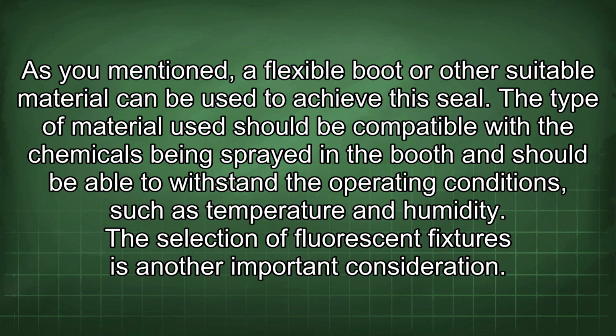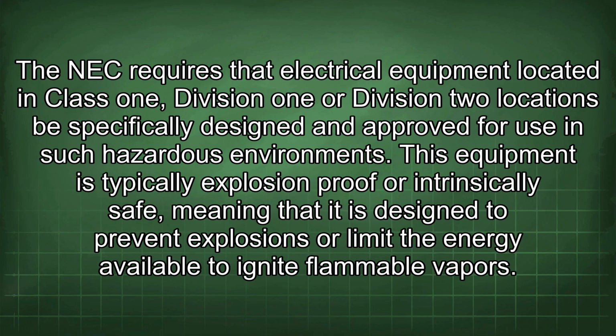The type of material used should be compatible with the chemicals being sprayed in the booth and should be able to withstand the operating conditions, such as temperature and humidity. The selection of fluorescent fixtures is another important consideration. The NEC requires that electrical equipment located in Class 1, Division 1 or Division 2 locations be specifically designed and approved for use in such hazardous environments.